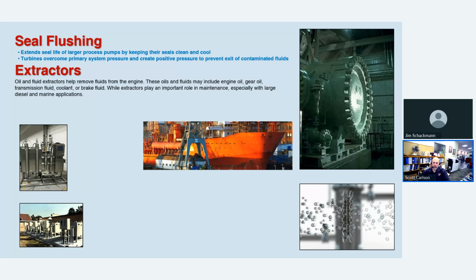Some of the other applications here, we have seal flushing and extractors. With the seal flushing, if you have an extremely large pump that is operating on a regular basis, and it's got a seal chamber inside of it that contains a very large seal that is very expensive to replace, you can run a line of fresh water using a regenerative turbine pump to overcome the amount of pressure that is being produced inside of the larger pump, just to go through the seal chamber to help keep the seal cool and keep contaminants from hitting the seal and ruining the seal. So you get a longer life out of that seal, and everything stays clean and cool inside of it.